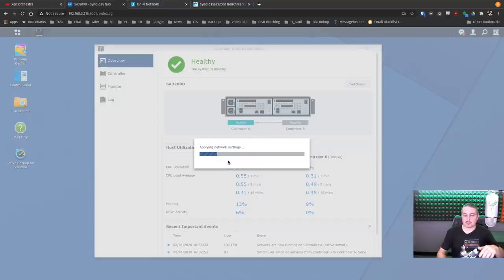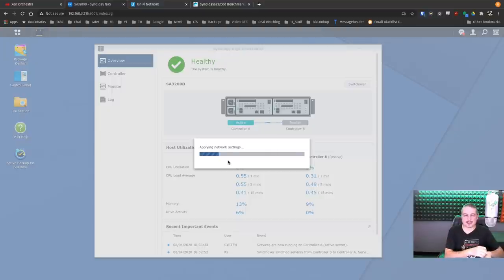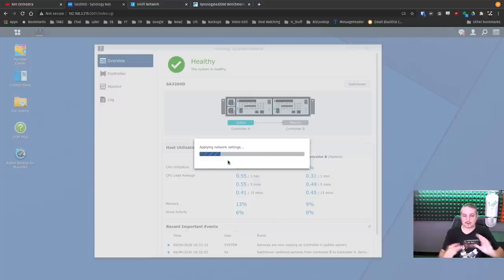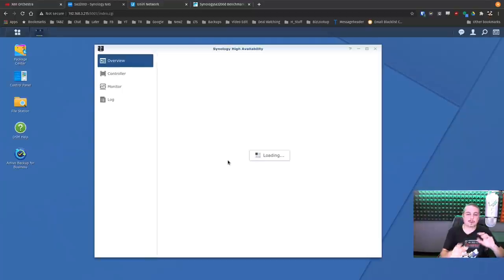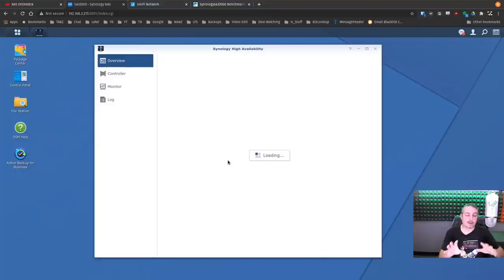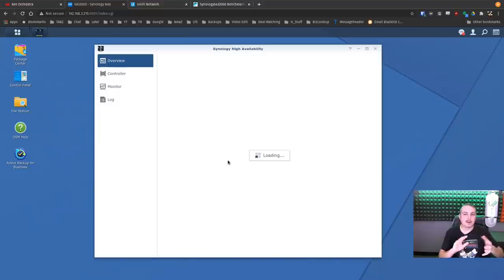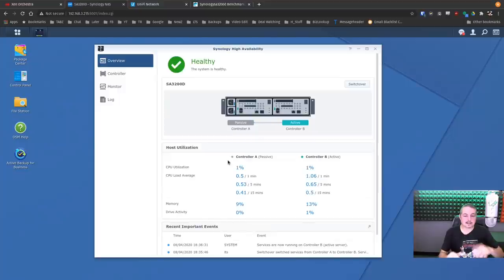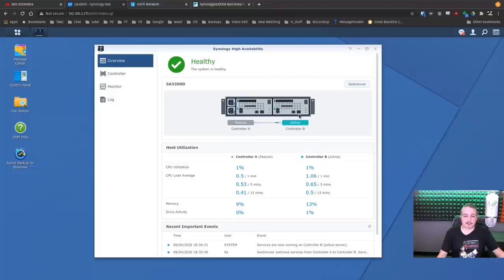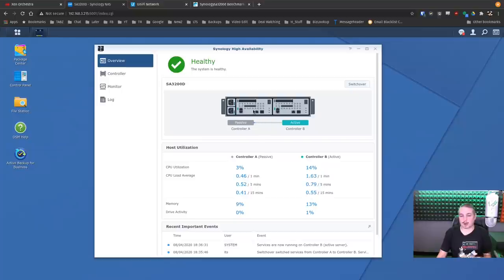This switches over relatively fast. This is the controlled one. It takes about 16, 17 seconds to do the switchover. This part takes a little bit longer, probably about 20 seconds. But if you were to ping it and see when the availability of the device is, it's about 14 seconds. The failover itself, like a catastrophic failover or just unplugging the network cable, takes pretty consistently between 49 and 50 seconds. So if we were to just unplug the system, it does take a little bit longer because it's looking for the network back and forth. When the controller failed, it paused a little bit longer while that controller was failed, and then it switches back over.